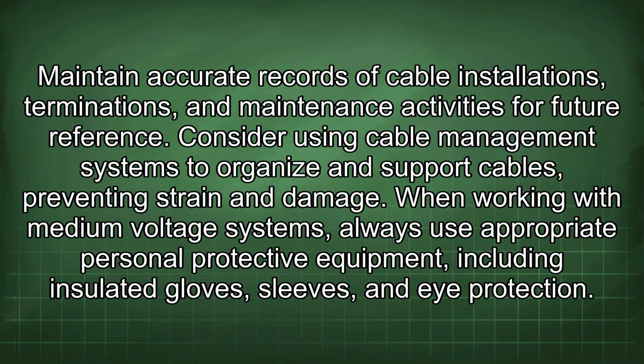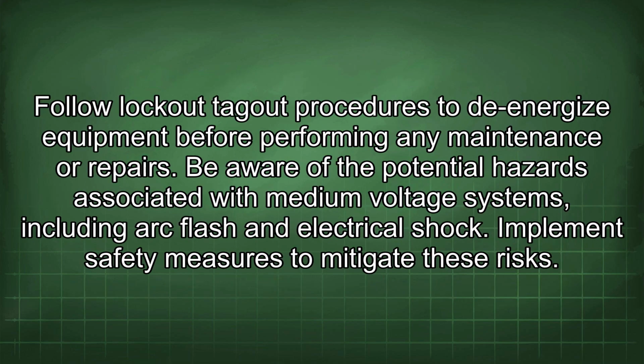When working with medium voltage systems, always use appropriate personal protective equipment, including insulated gloves, sleeves, and eye protection. Follow lockout-tagout procedures to de-energize equipment before performing any maintenance or repairs. Be aware of the potential hazards associated with medium voltage systems, including arc flash and electrical shock. Implement safety measures to mitigate these risks.